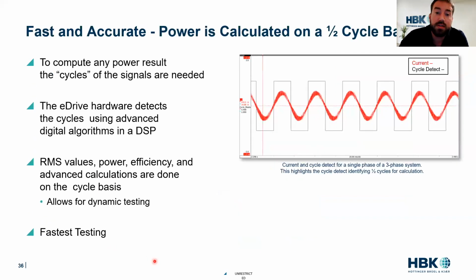We're really good at this. We use an algorithm called cycle detect, where we can actually track the fundamental frequency and give a calculation of power factor, all of that, every half electrical cycle. We do this in our digital signal processor, so this is all happening real time, which allows us to test extremely quickly and accurately measure power and power losses in scenarios like flight sequences, where you have startups or might have bird strikes, these types of scenarios.